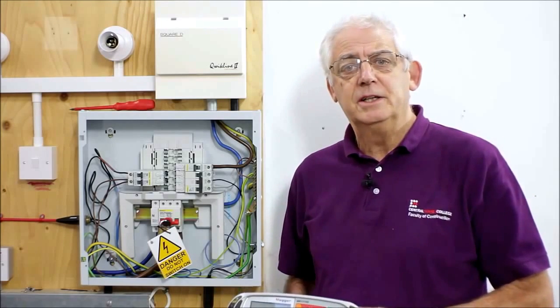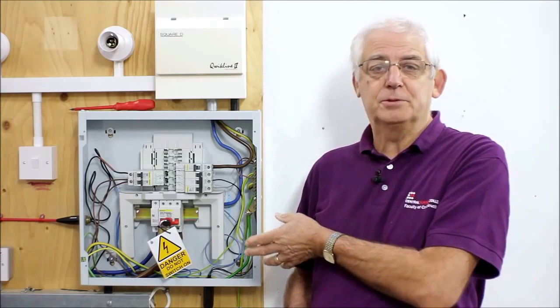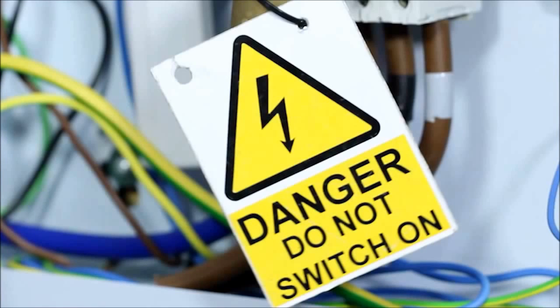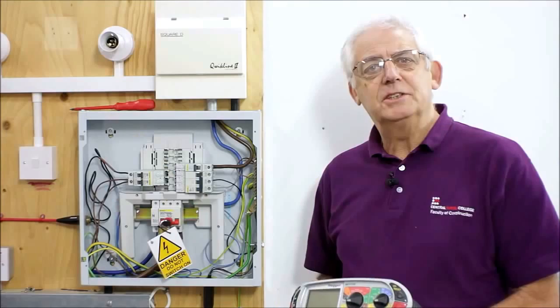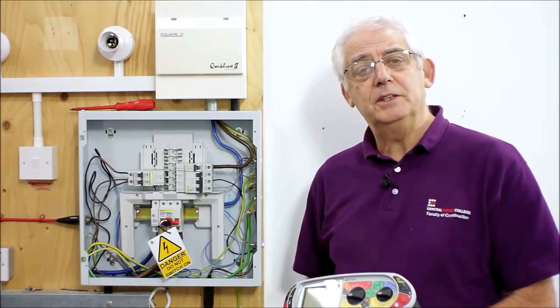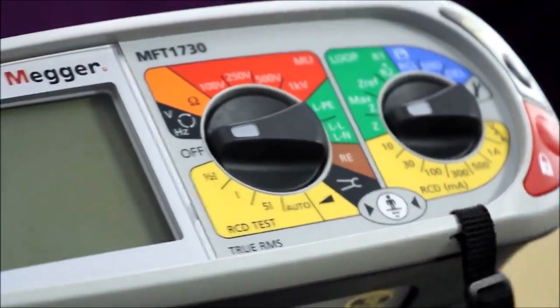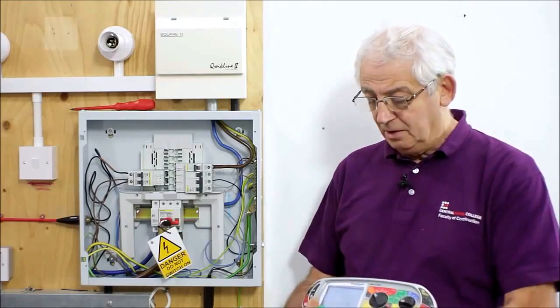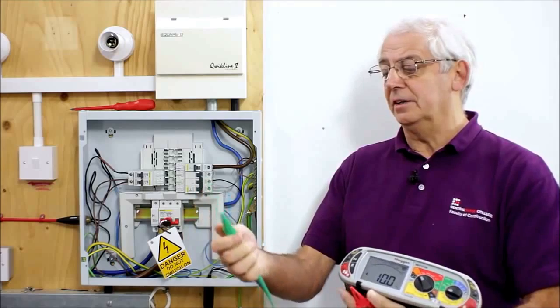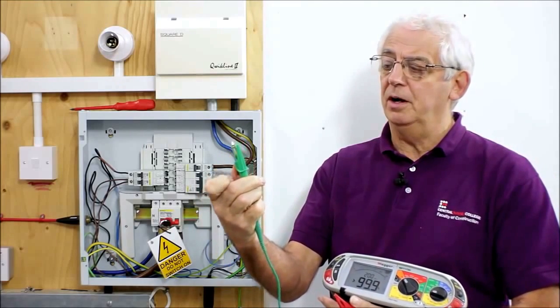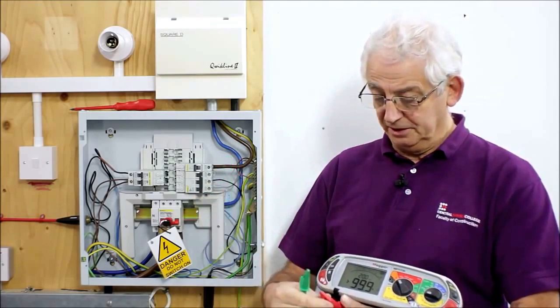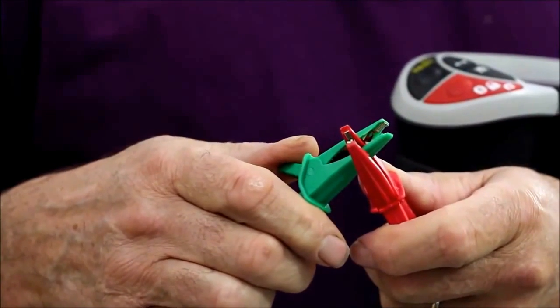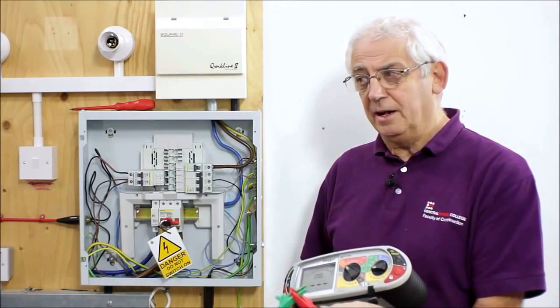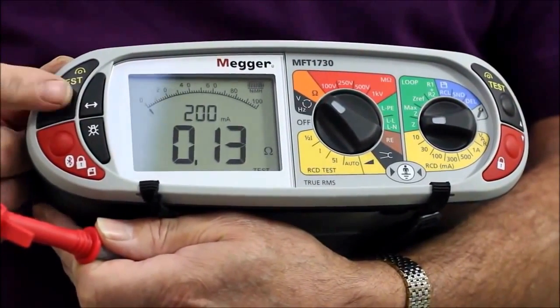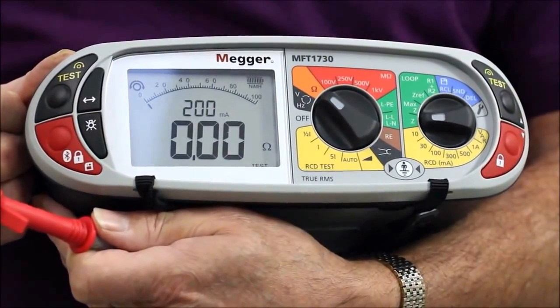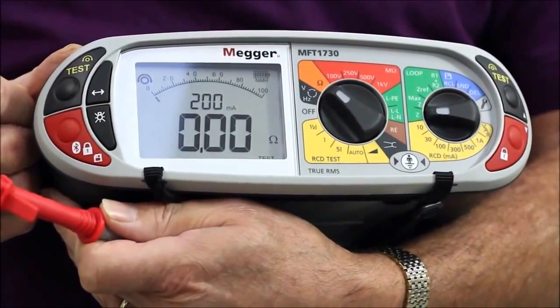There's obviously other ways. First of all, we need to make sure that the board is absolutely isolated, locked off as it should be. We need to use a low resistance ohm meter. Obviously we need to zero the leads, so if we do that before we start, turn the instrument on. When we connect the leads together, we need to make sure that we've got the solid part of the crocodile lead touching the solid part of the other crocodile clip so that we don't end up with high resistance joints. Once I've got a reading, if I push the button, zero the instrument, that's that part of the job carried out.